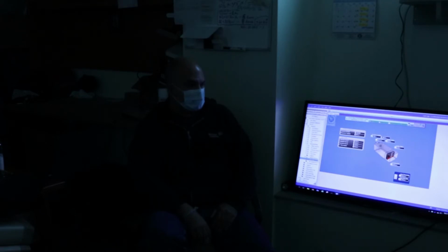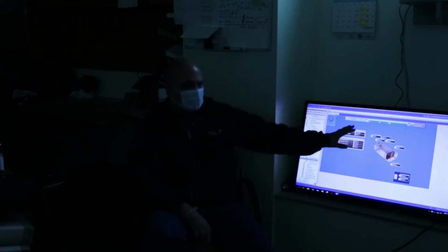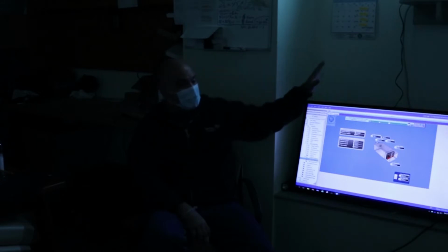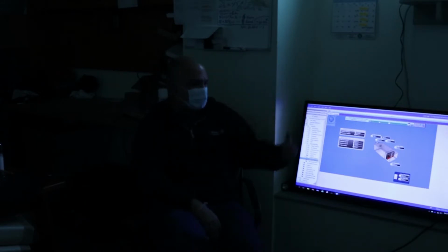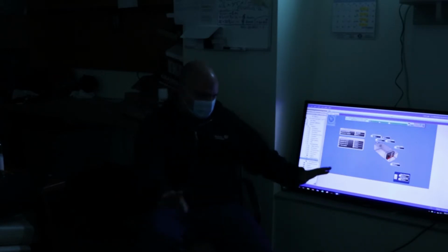If you open a thermostat in a transportation supervisor office, you will see the difference. It's a VAV, I'm talking NRB. You've got to remember, my mind is completely set in NRB because I didn't do any of the work in CSP. In the CSP, in the transportation supervisor office, the dead band is like 10 degrees on the other side. Our standard default is 2 degrees.